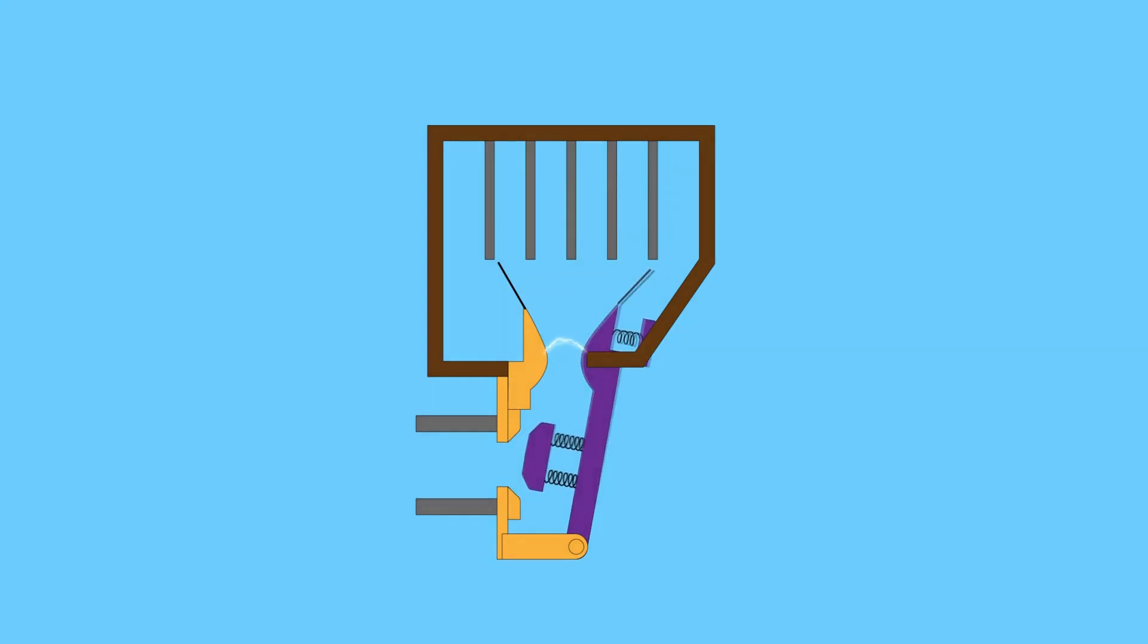When the main contacts open, the arcing contacts are still in touch with each other. The current gets a parallel low resistive path through the arcing contact. During the opening of the main contacts, there will not be any arcing in the main contact. The arcing is only initiated when the arcing contacts are finally separated.